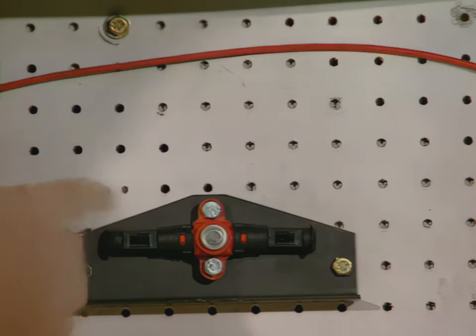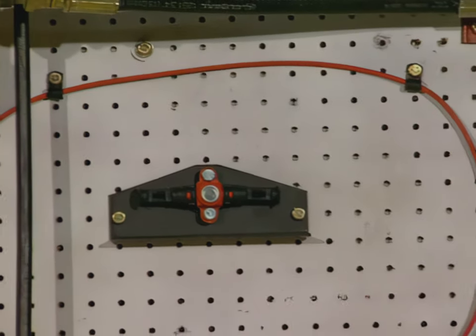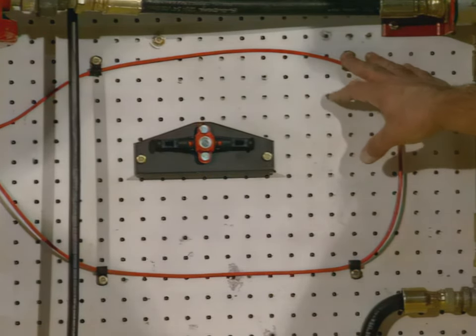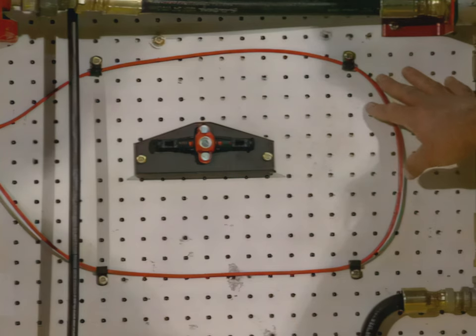There is also a thermal detector. You're going to have the same problem with this detector as with the detection wire: if you get a coat of anything on it — mud, paint, anything — it's going to change the rating on that particular unit and it will no longer perform at the same rating.